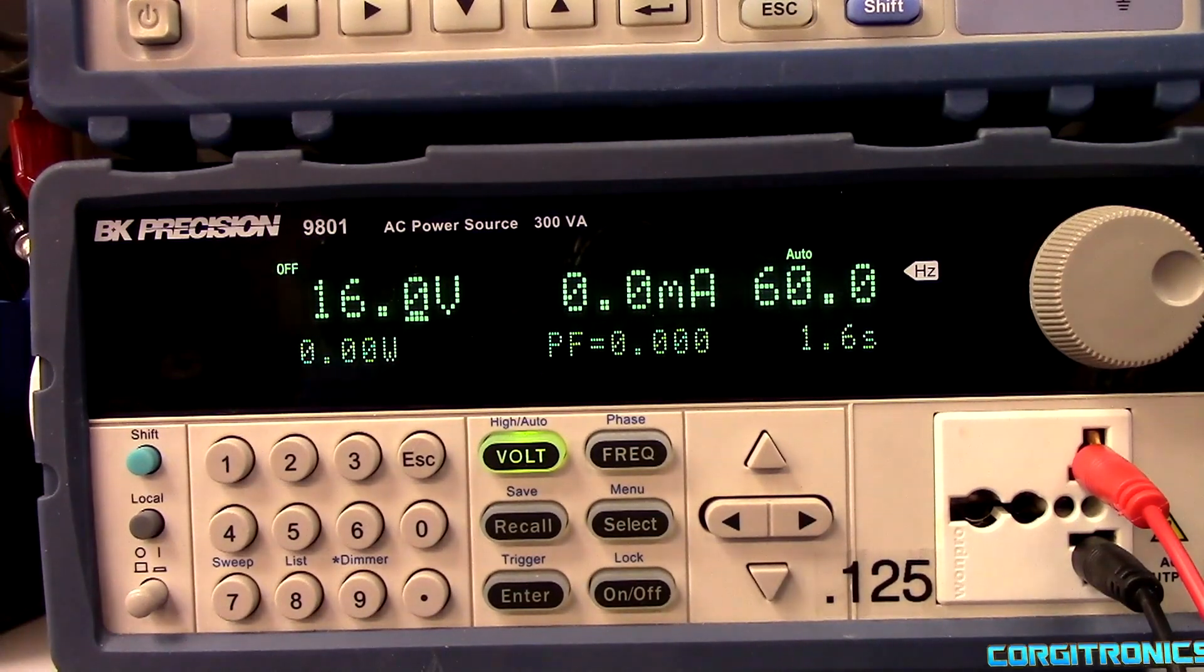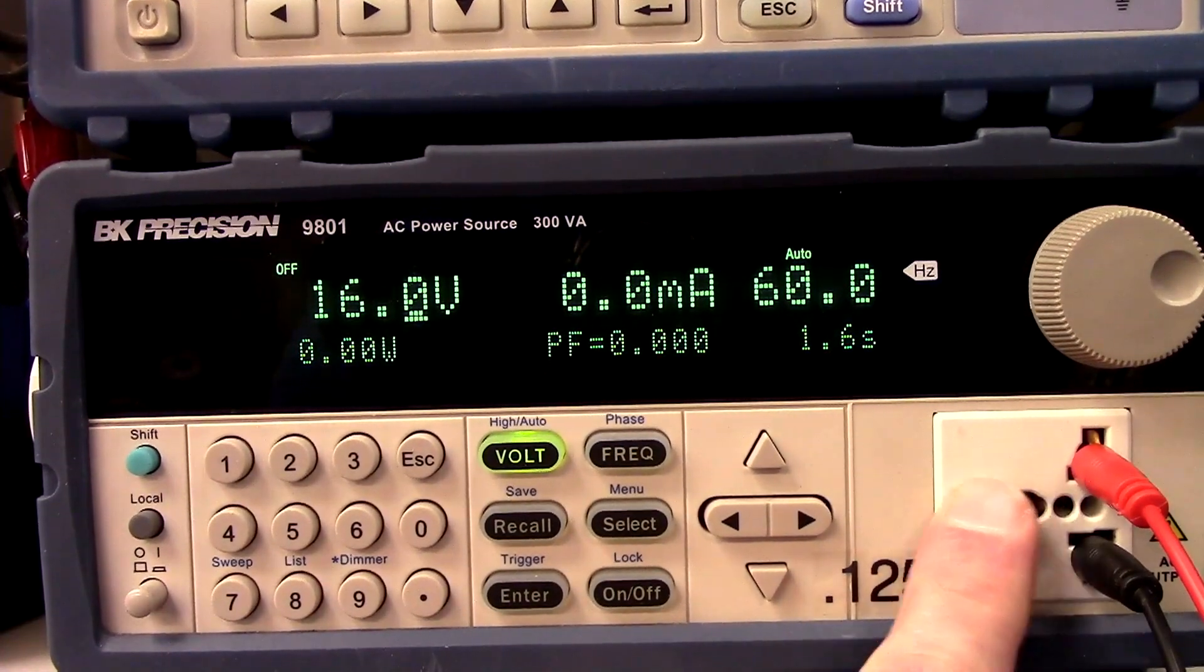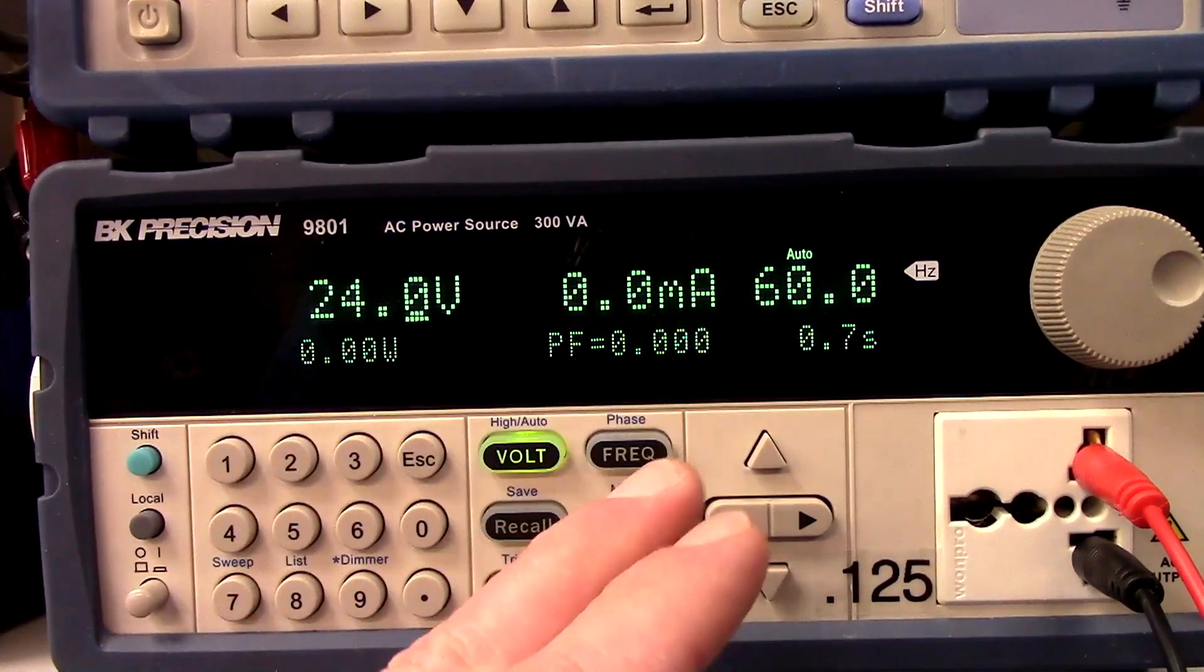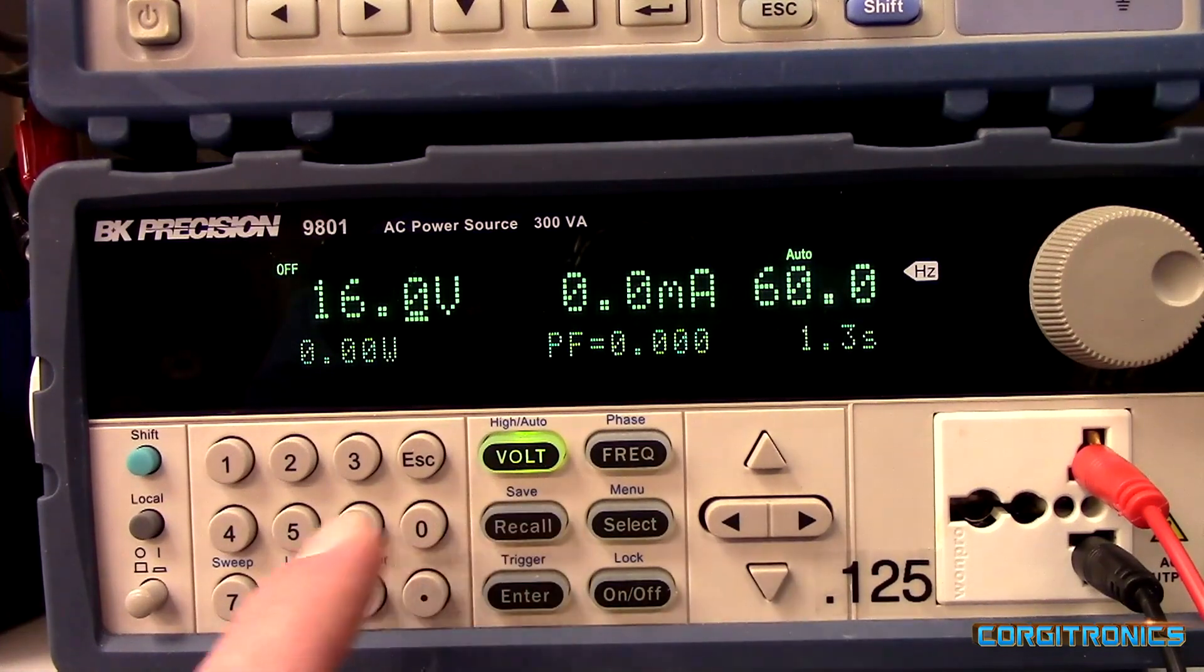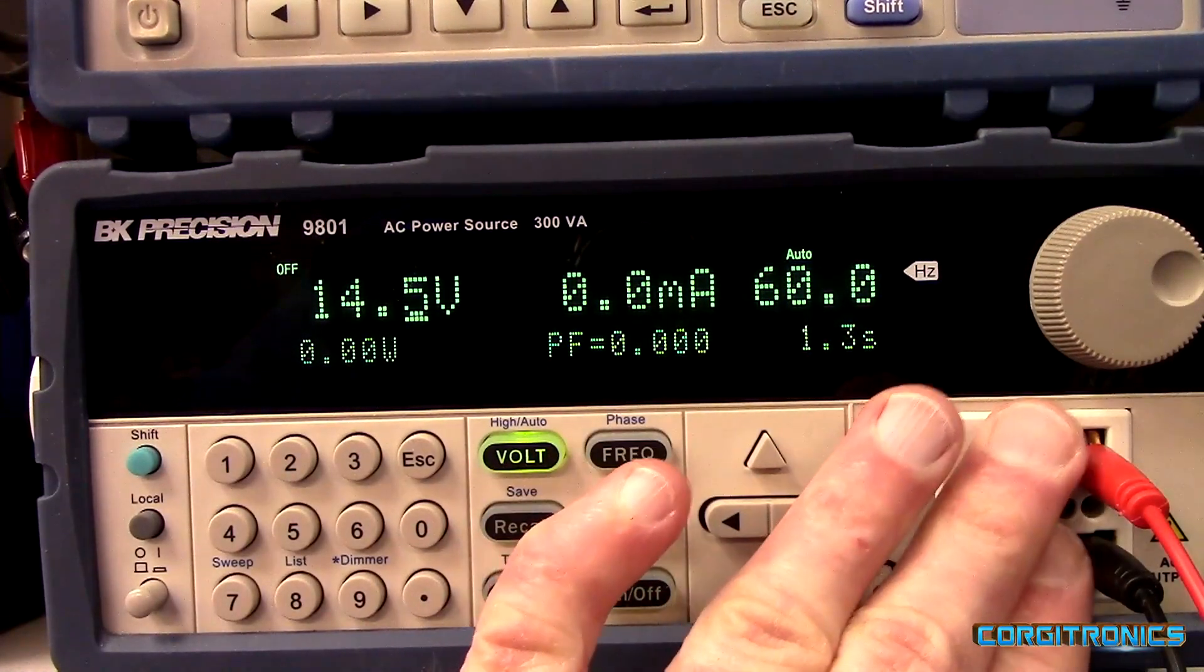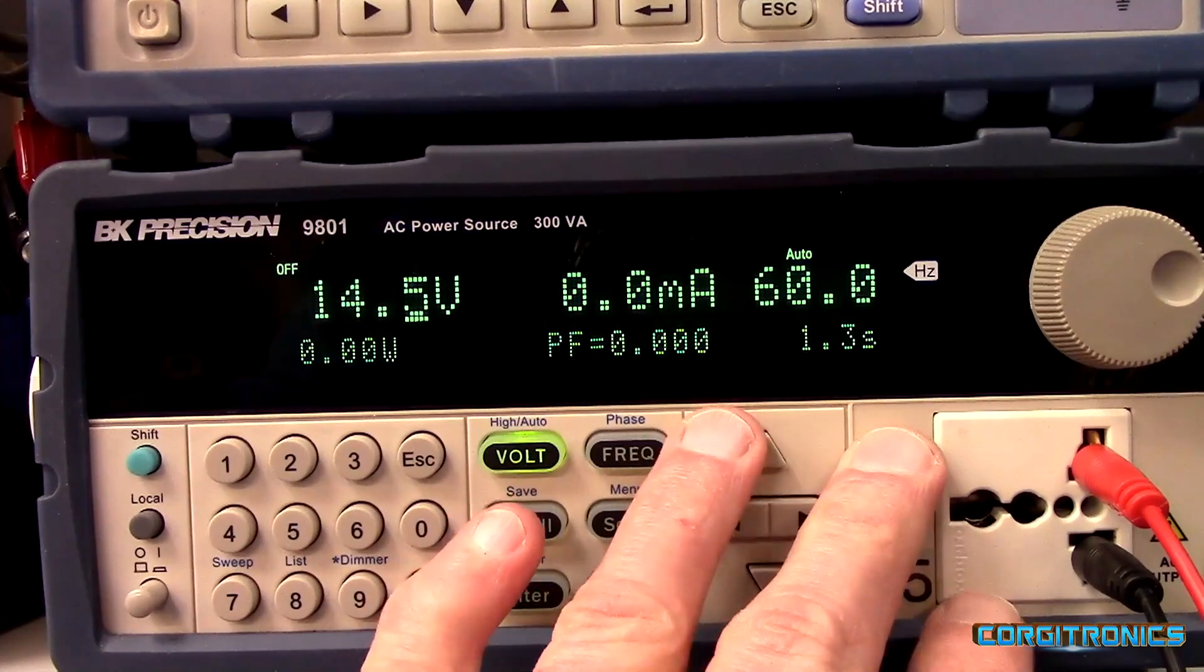Now to test this out, I've got a nice BK Precision 9801 AC power supply here, and that provides AC voltage up to 300 volts AC. The nice thing is that I can dial in any voltage I want. I can set it to 24 and we get 24 out, or just 16. And say your transformer was a little weak, we can set it to 14.5 and we can test the relays at that. The nice thing is this is isolated AC output, so it's safe from mains electric shock. It's the same as using a regular transformer, except that this is very controllable. I can control the amount of current and voltage.